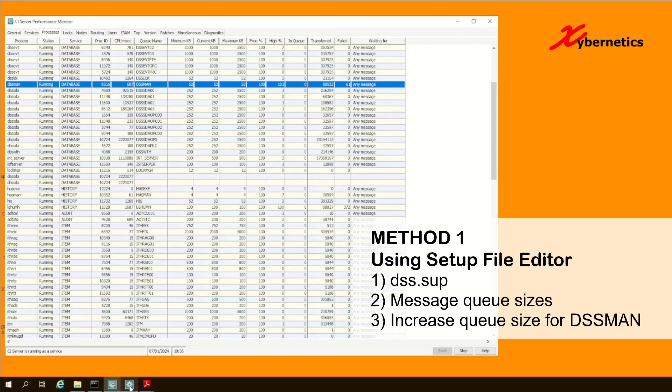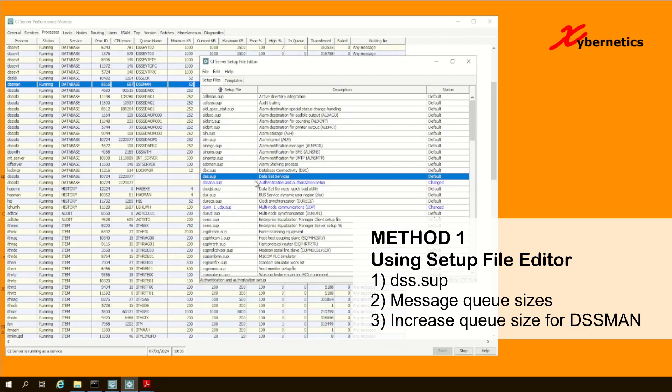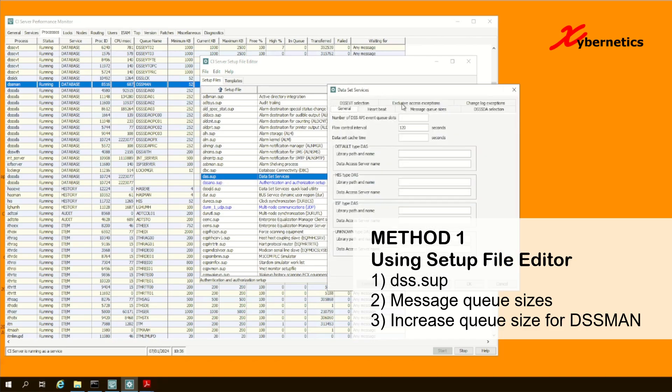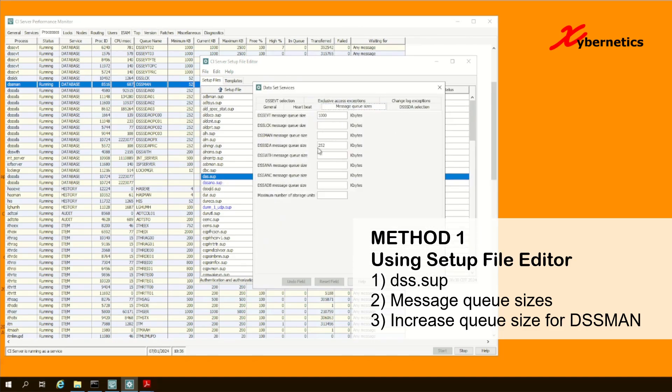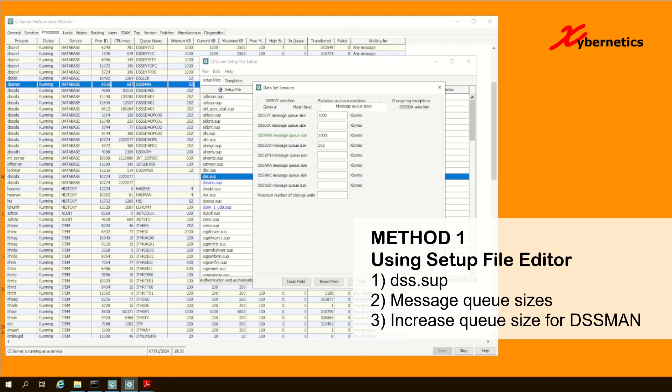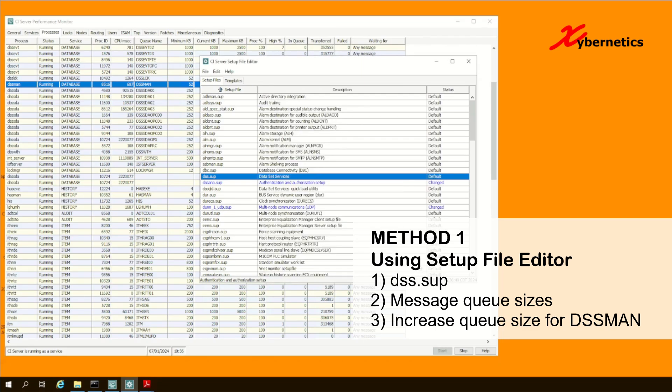If you launch a setup file editor like this, under DSS SUP, if you double click on it and you go under the message queue size here, you can actually increase this to a thousand like this and hit OK. The only difference is that once you make a setup file editor change, you're going to have to restart your CI server.